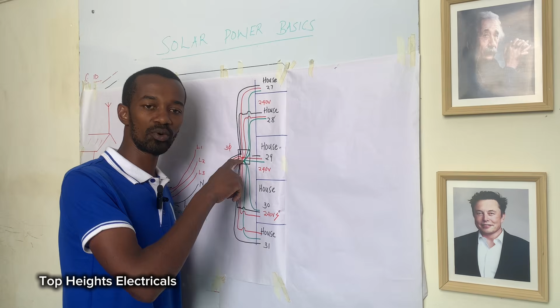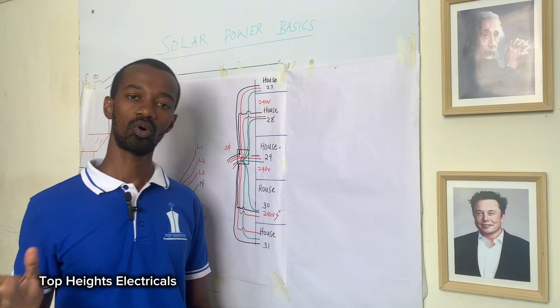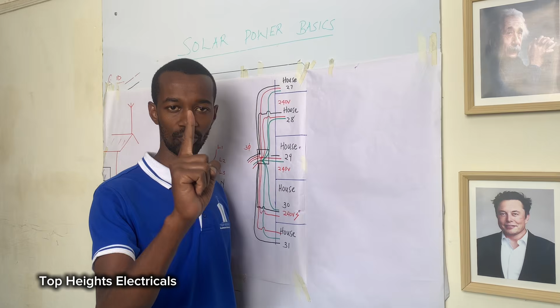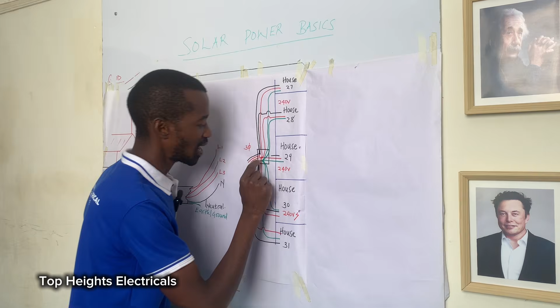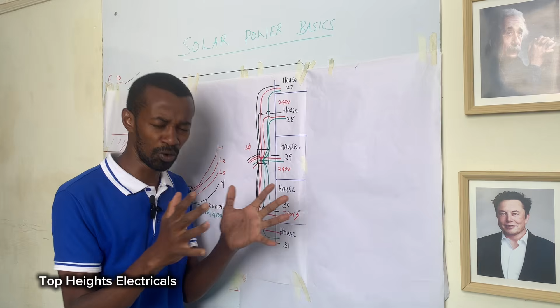Our advice was that the customer has to come up with her own earth connection, an earth rod, not just one, two, or even three, until we get values below 5 ohms, to ensure the earth resistance is very low. In that case, connect the customer, and only the customer, one earth connection for one household, disconnecting her from the community earthing and having the earth rod solely for her household. That is the only way we can achieve safety in her home.